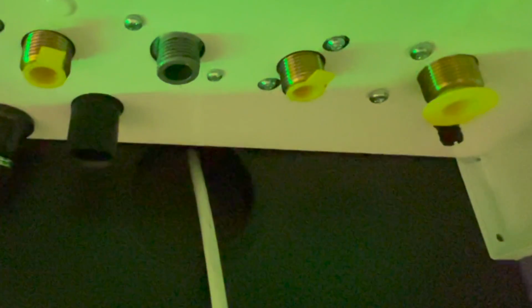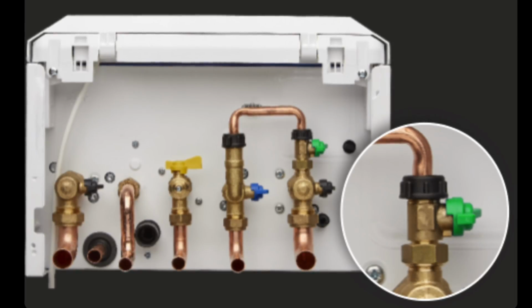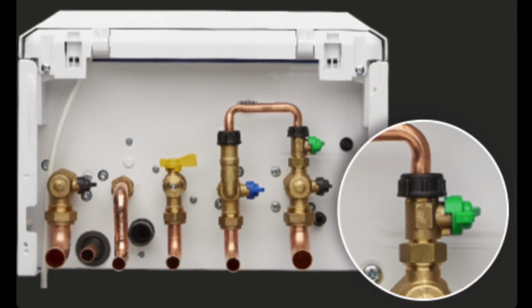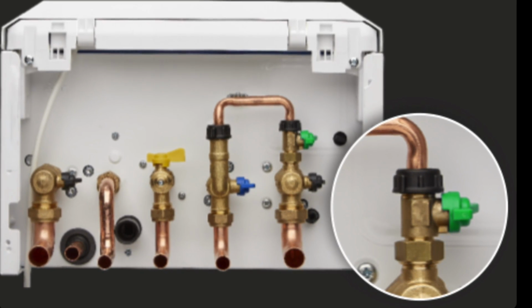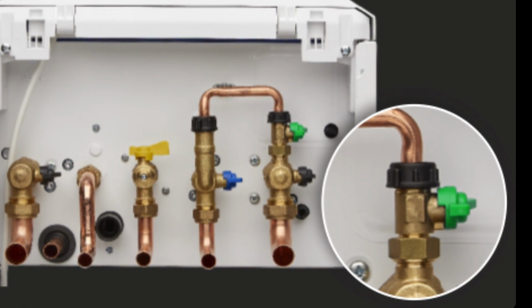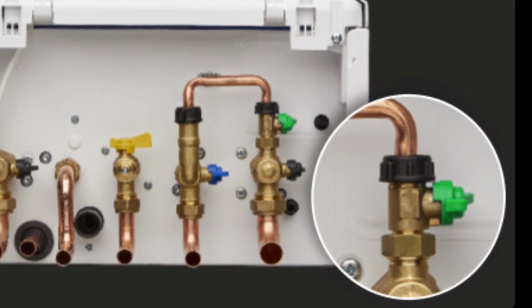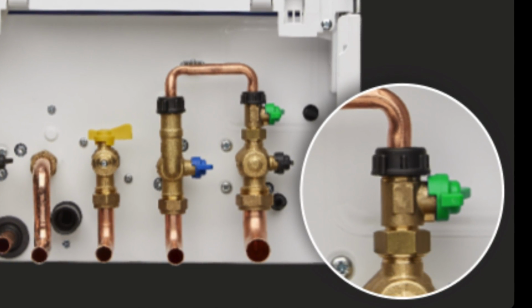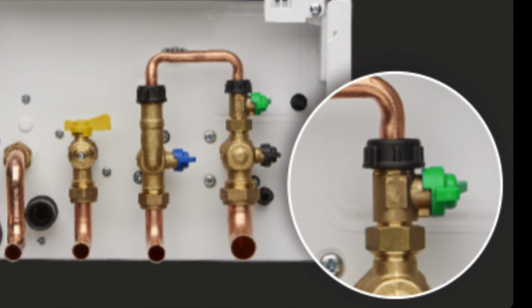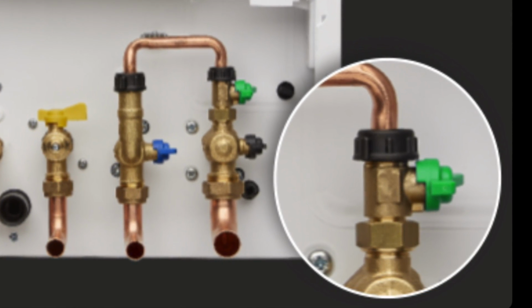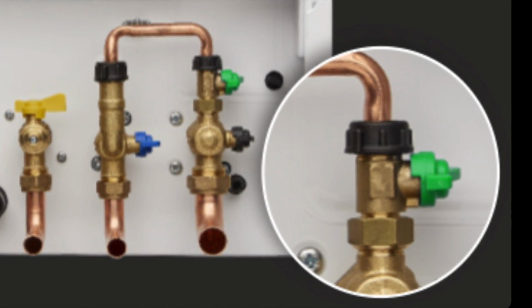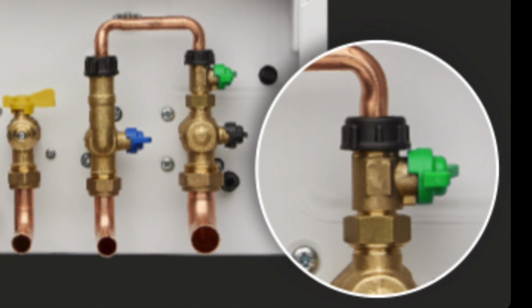The condensate now is closer to the wall, so it could actually make it a little bit harder putting your condensate pipe in. And obviously if you're changing this boiler from an old gen, then you're going to have to move the blow-off. Now one of the changes made underneath the boiler is one I don't really understand why they've done it, but they've changed the colour of one of the handles on the filling loop. The valve on the return side now is this green colour, rather than having 2 blue handles. I guess the only reason they've done this is to help customers identify which valve is which when they need to top up the boiler.